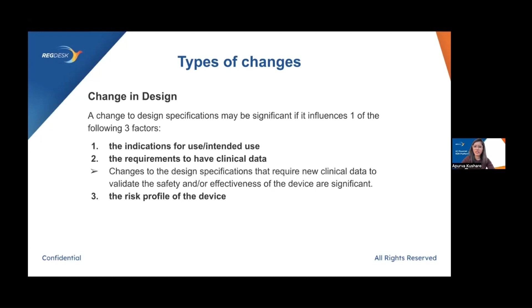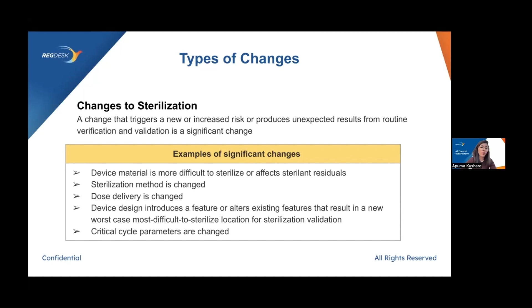The next type of change that the guidance document has stated is changes to sterilization. Any change that triggers a new or increased risk, or production which produces any unexpected results from routine verification and validation, is considered to be a significant change. So we have some examples of significant change pertaining to sterilization. In one scenario, the device material is more difficult to sterilize, or it affects the sterilant residuals. This can lead to a significant change. Another example would be if you're changing the sterilization method altogether, or changing the dose delivery of the agent that you are using. Also, if any critical cycle parameters are changed, that would be considered a highly significant change.